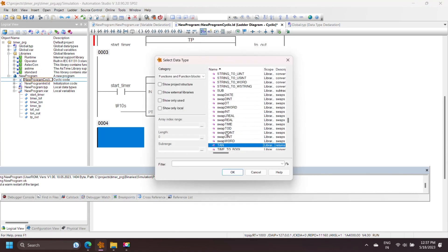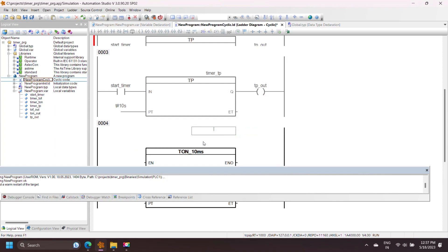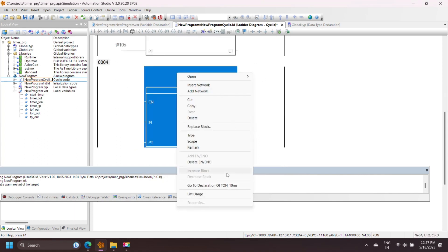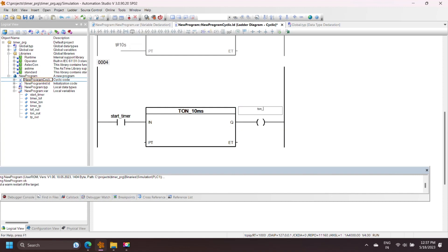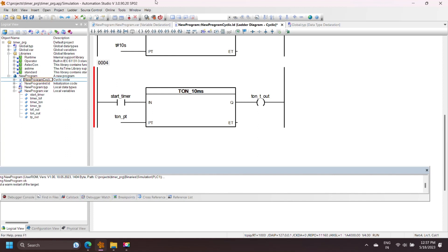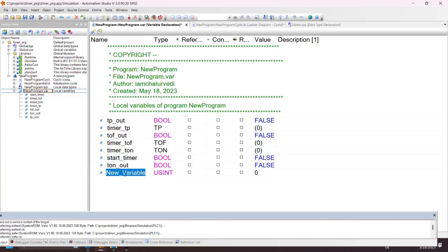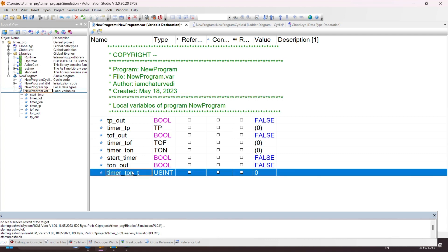B&R Automation Studio also has three special timers. These timers have preset value and elapsed time in signed double integer (DINT) data type. These instructions are used when a process requires a manual time value so we can directly enter a value without conversion. For example, if the preset value is 1000 then the timer operation time is 10 seconds. The operation of these timers is the same as normal timers. For example, TON_10ms is an on-delay timer with a 10 millisecond base. Normal timer preset value uses the time type (e.g., T#15s), but these special timer preset values use signed double integer — if the value is 1000, the timer operation time is 10 seconds.